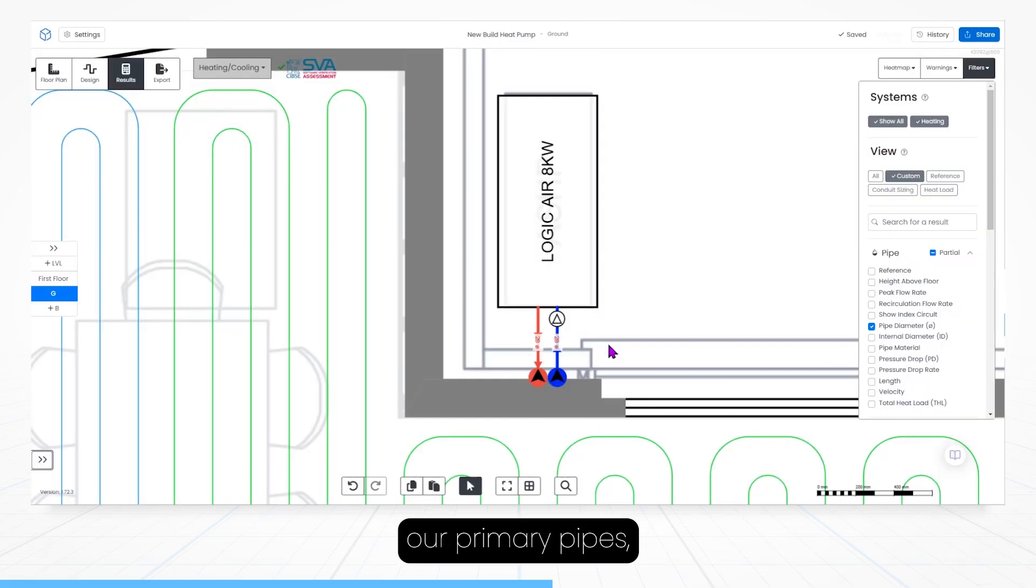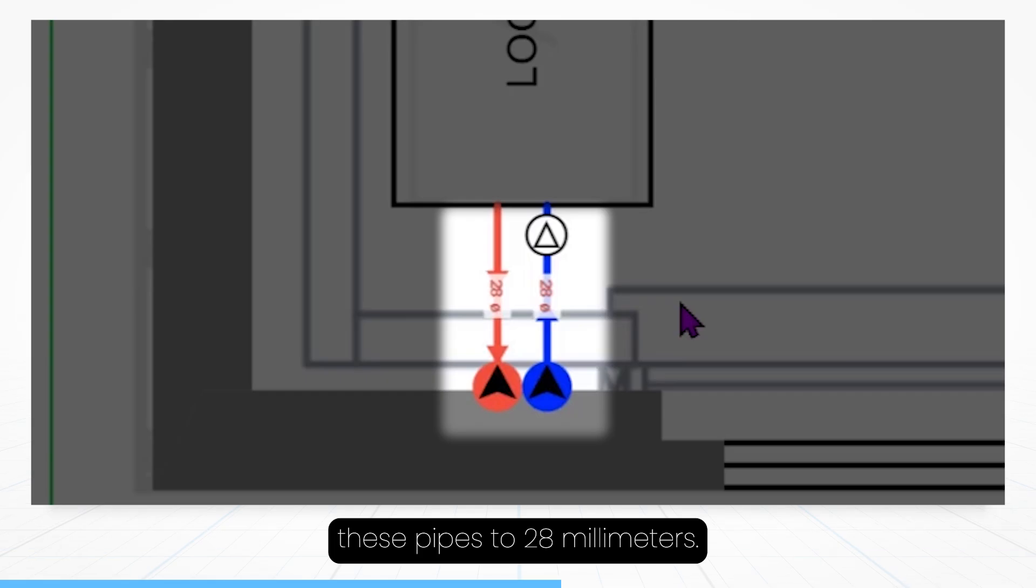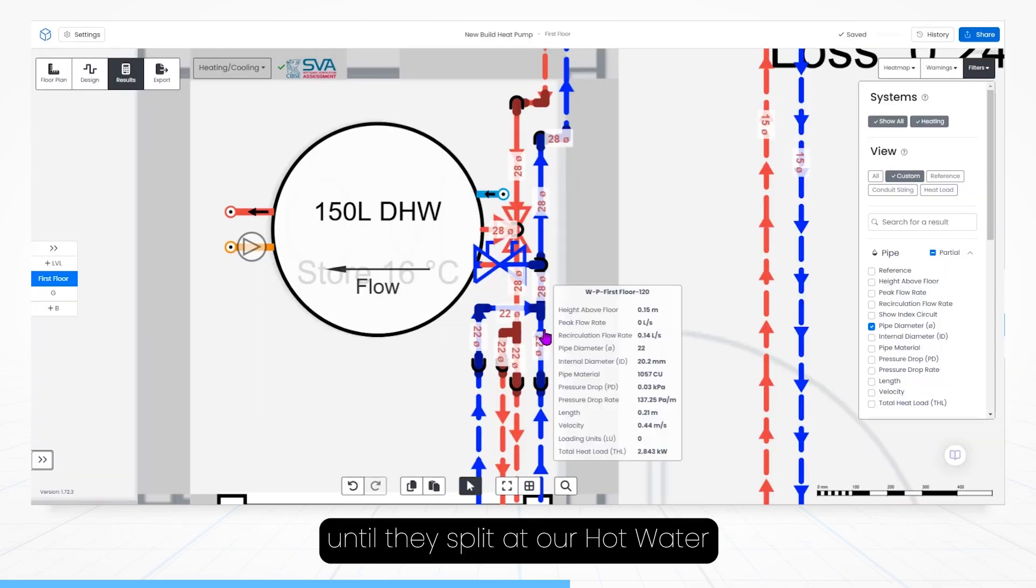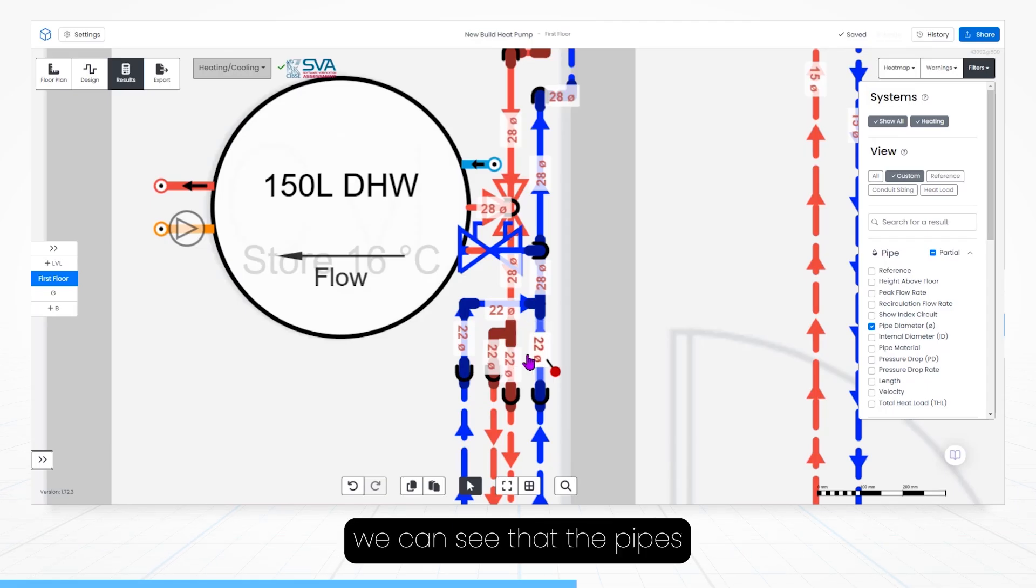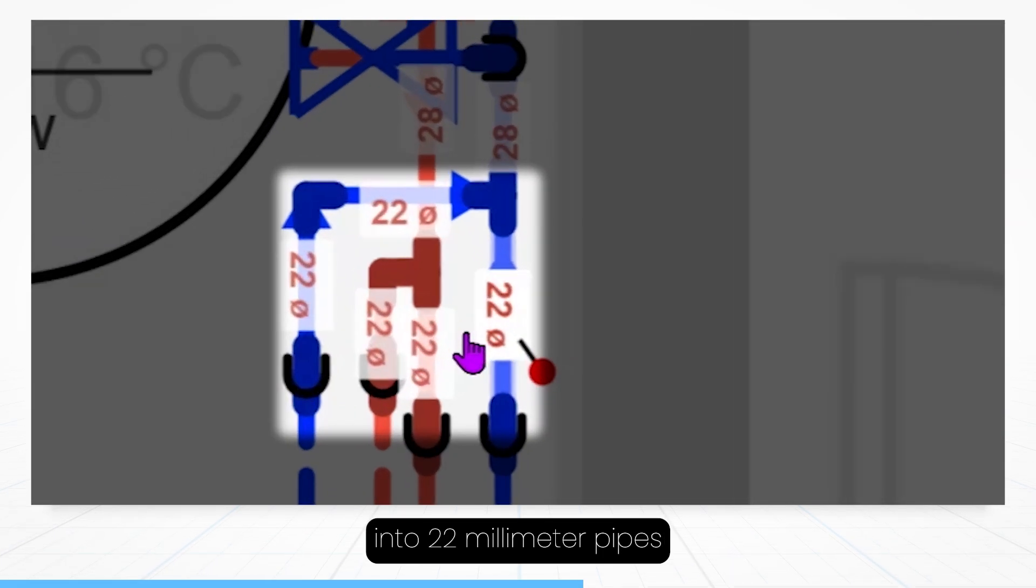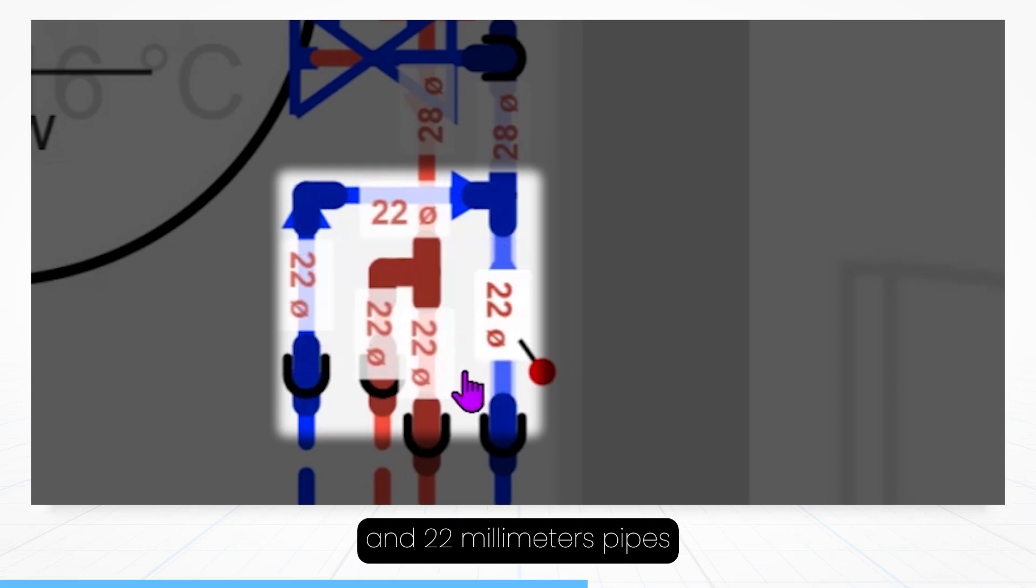So zooming in on our primary pipes, we can already see that the system has automatically sized these pipes to 28mm. And following the primaries up until they split at our hot water cylinder and diverter valve, we can see that the pipes are automatically resized into 22mm pipes for the radiator zone, and 22mm pipes for the underfloor heating zone.